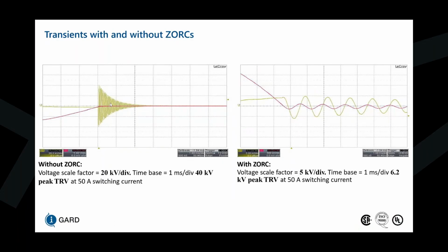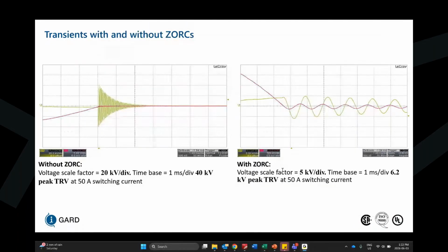The C2 line, I'd have to inquire on that one. But I'm mostly focusing on the yellow line where we're seeing a lot of high switching transient for that short duration of just over 2 milliseconds.